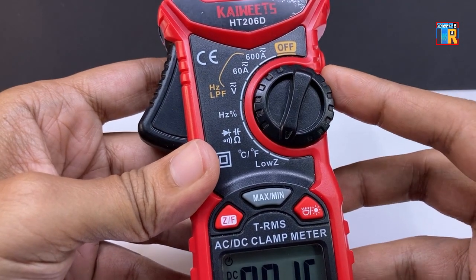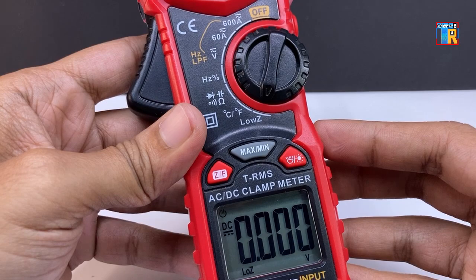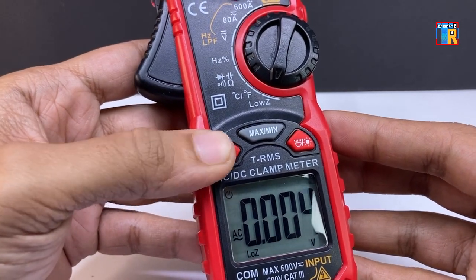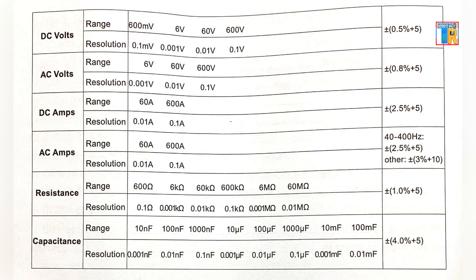This is a low impedance voltage measuring mode. You can measure voltage in this mode to avoid any ghost voltage. Here you can see the testing range of this meter.